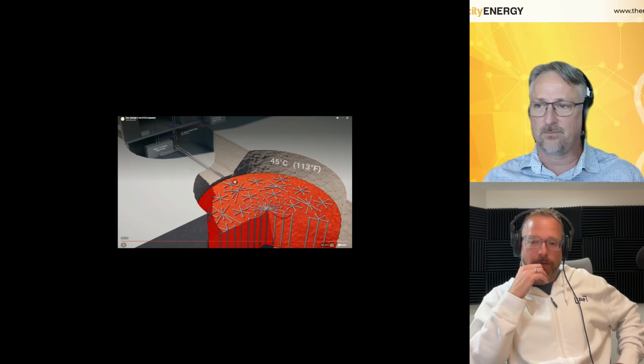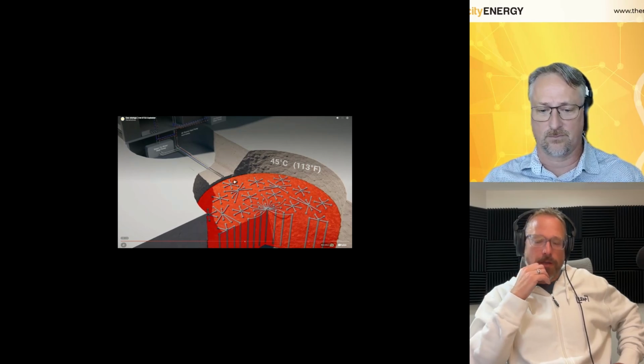So this really offers a long duration thermal energy storage solution that, if you were to stack this up against, let's say, lithium ion batteries, it sounds to me like no contest. But you tell me. It is no contest, but they're different purposes. Lithium ion batteries are really good for the 4-hour duration, trying to meet your peak load. We're storing over a season. The cost of lithium ion batteries is somewhere in the range of $250 to $500 a kilowatt hour. We're at less than 50 cents a kilowatt hour.